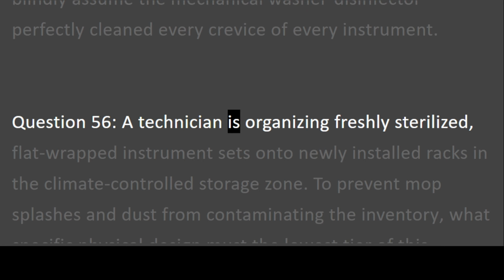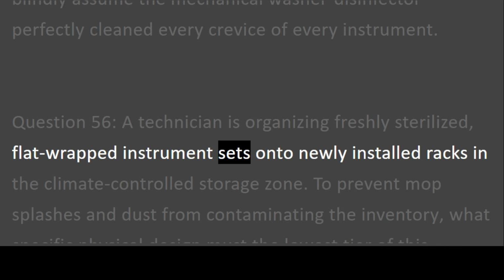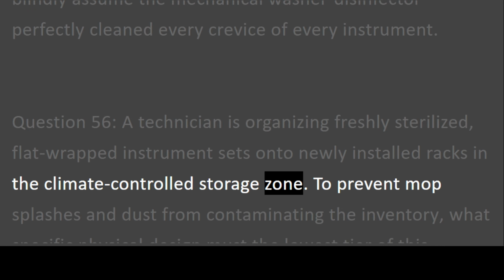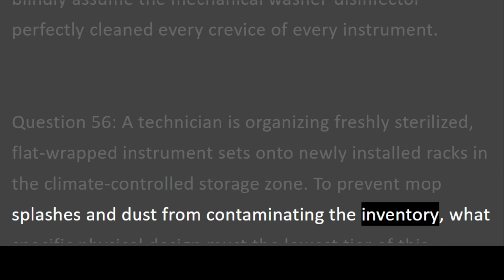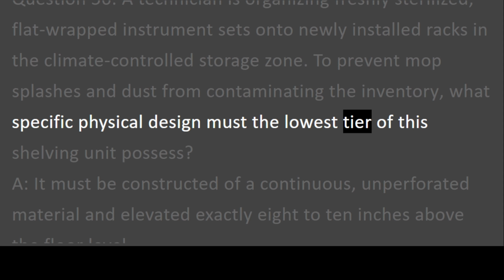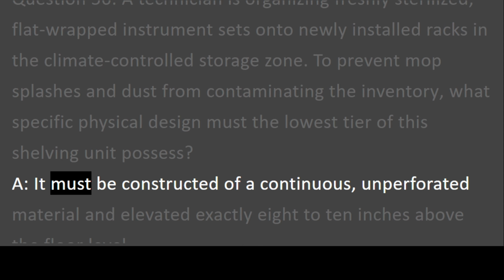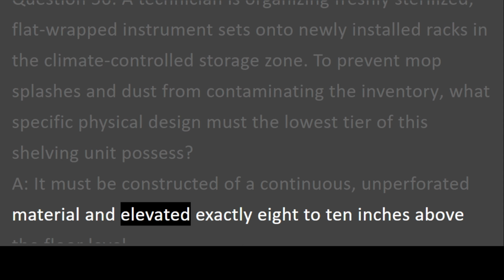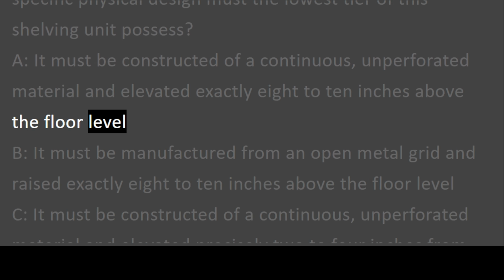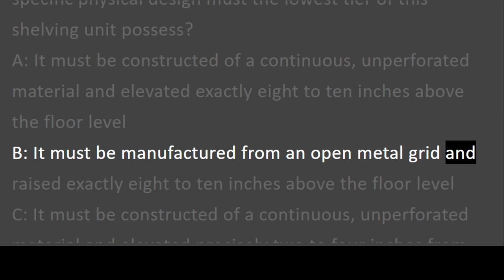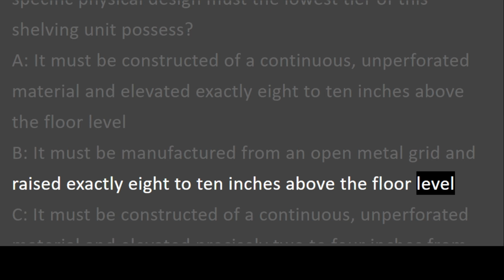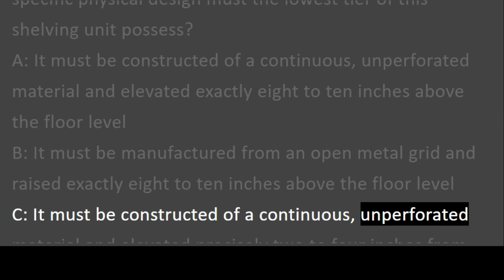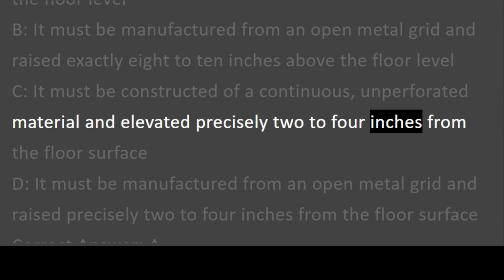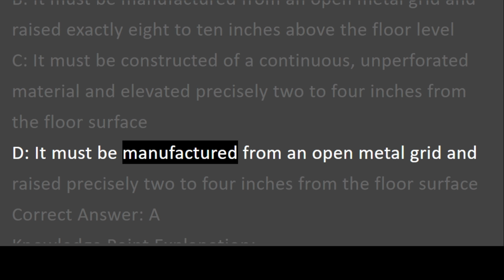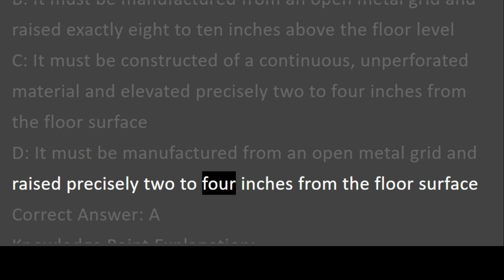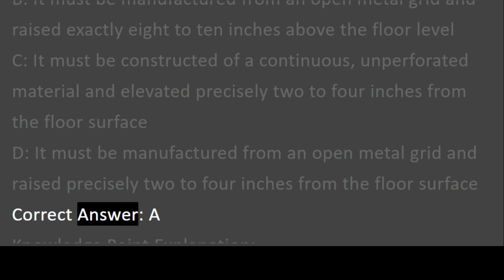Question 56. A technician is organizing freshly sterilized, flat-wrapped instrument sets onto newly installed racks in the climate-controlled storage zone. To prevent mop splashes and dust from contaminating the inventory, what specific physical design must the lowest tier of this shelving unit possess? A. It must be constructed of a continuous, unperforated material and elevated exactly 8 to 10 inches above the floor level. B. It must be manufactured from an open metal grid and raised exactly 8 to 10 inches above the floor level. C. It must be constructed of a continuous, unperforated material and elevated precisely 2 to 4 inches from the floor surface. D. It must be manufactured from an open metal grid and raised precisely 2 to 4 inches from the floor surface. Correct answer, A.